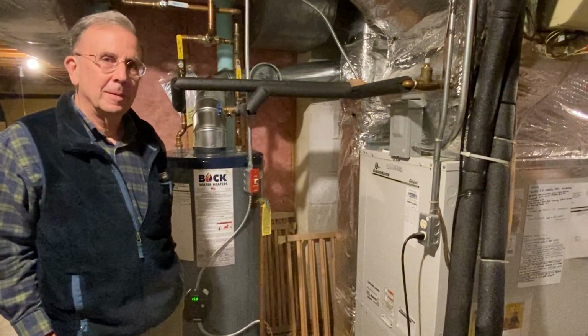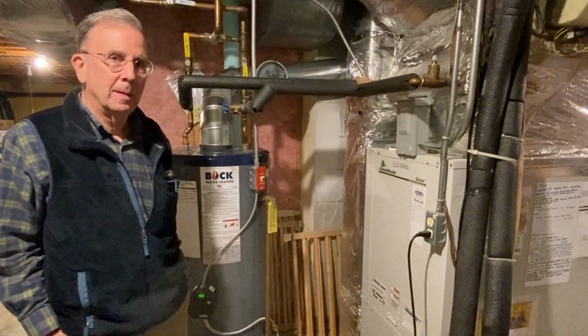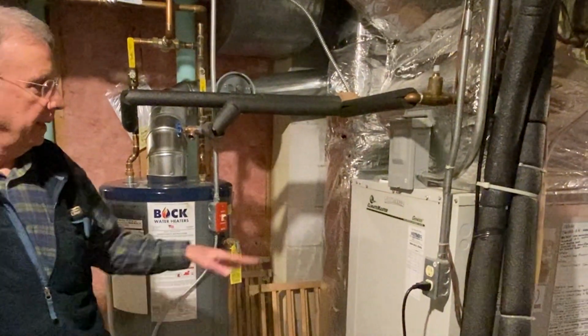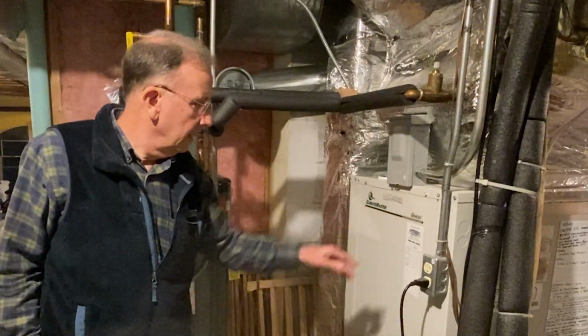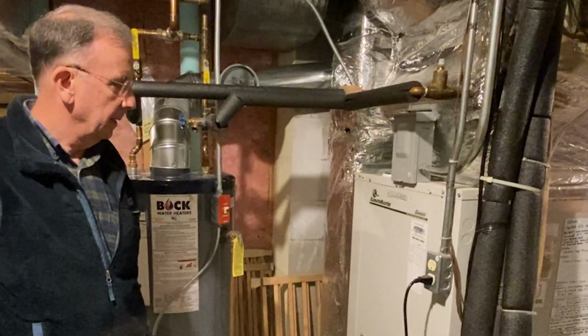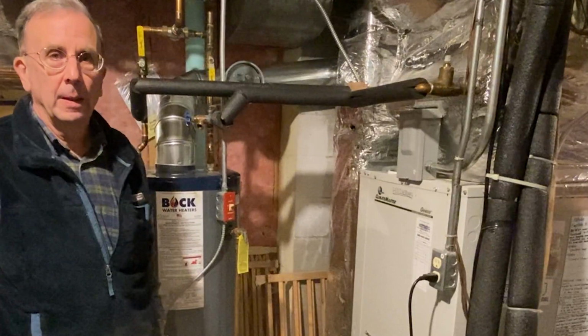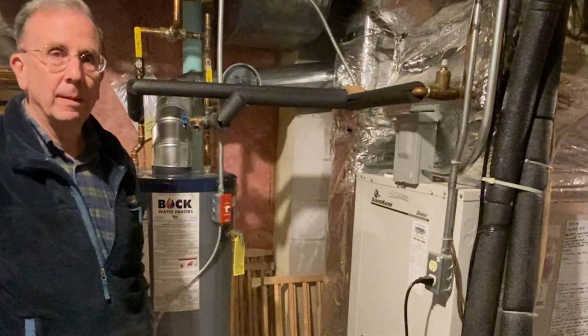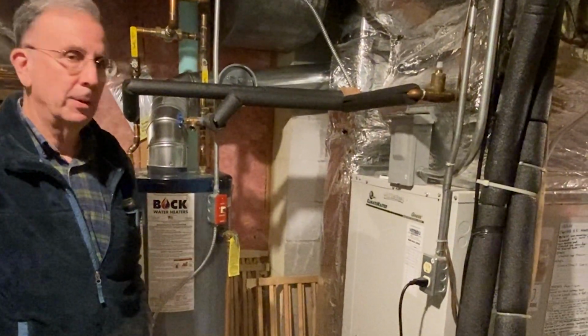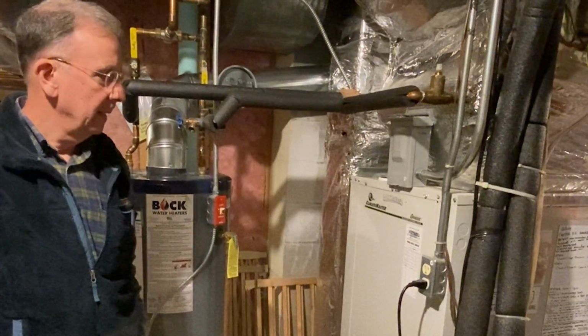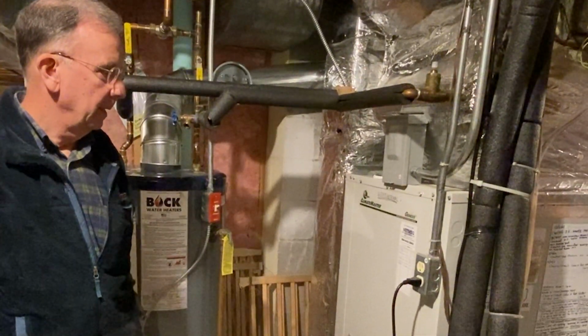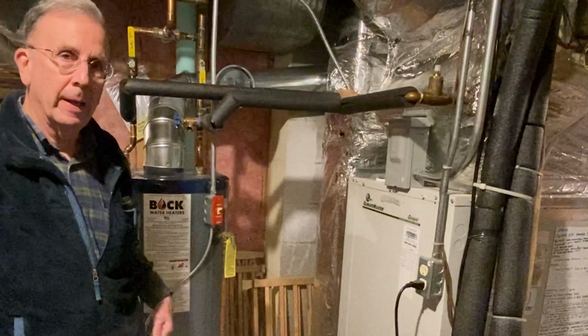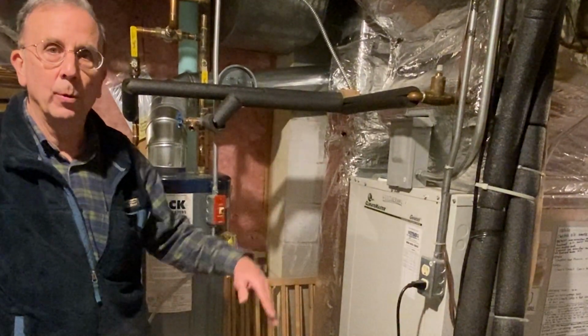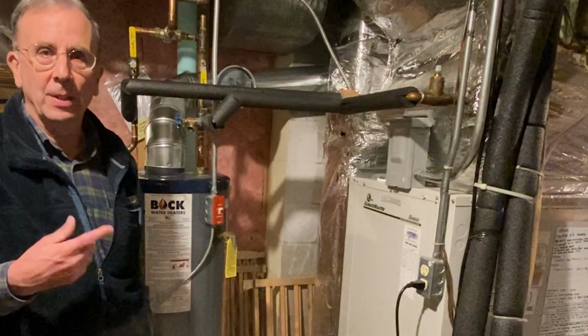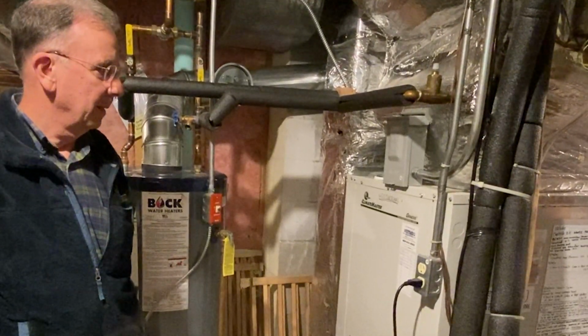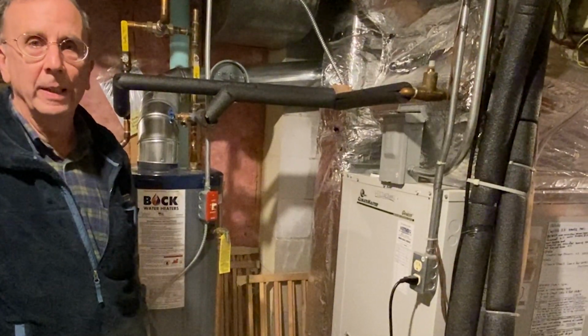Okay, so this is a system. Can you tell us a little bit about it? Yeah, so this is the actual heat pump unit. The compressor that is connected to the loops will extract heat in the wintertime from the fluid that's being pumped in from the outside. And in the summertime, it will take heat out of the house, and the fluid will then go through the loops and be cooled again, and then cycle through the process to give us the cooling in the summertime.